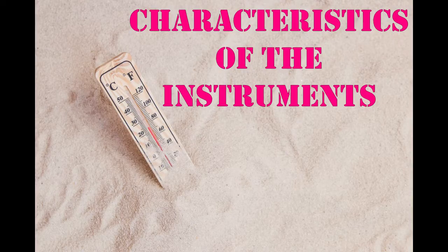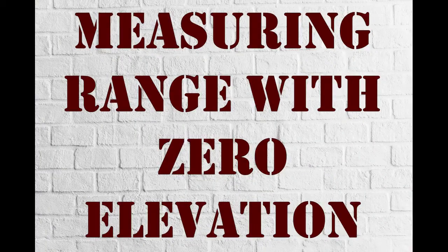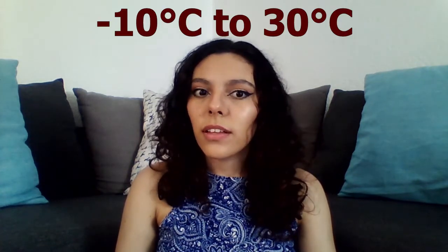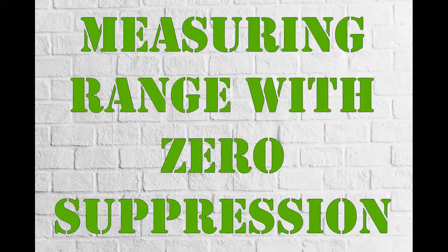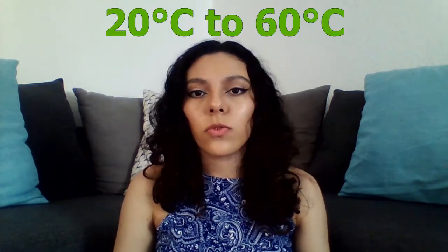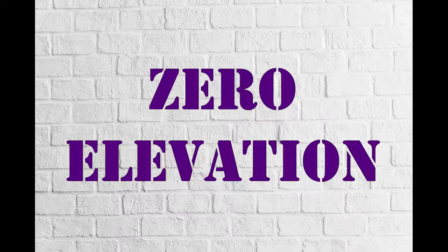Welcome to my channel. Today I'm gonna talk about the measuring range with zero elevation. It is the measuring range where the zero value of the measured variable is greater than the lower value of the measuring range. For example, minus 10 to 30 Celsius. The measuring range with zero suppression is the measuring range where zero is less than its lower value. For example, 20 to 60 Celsius.